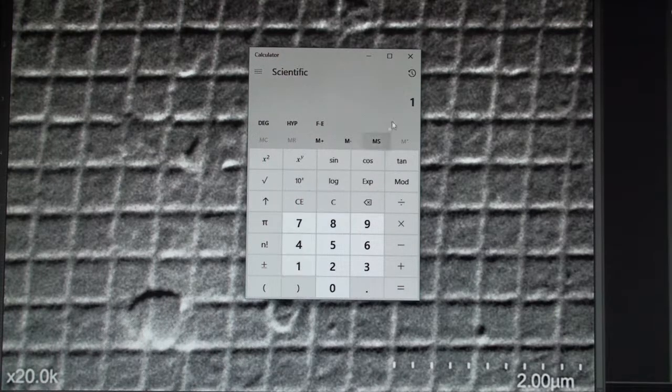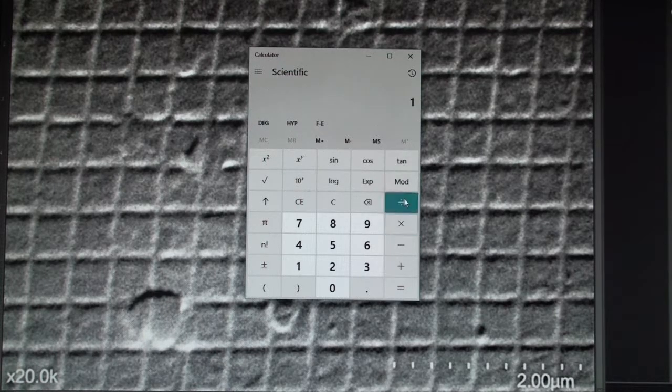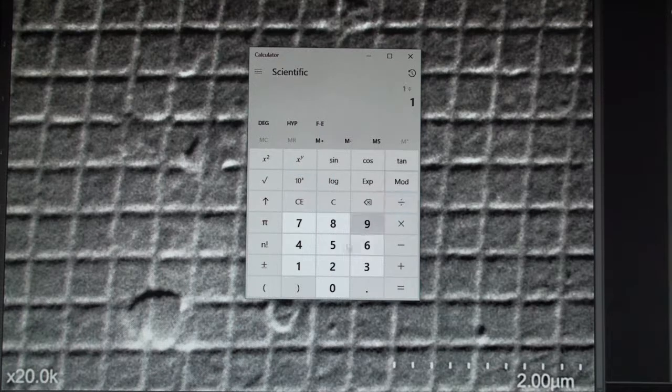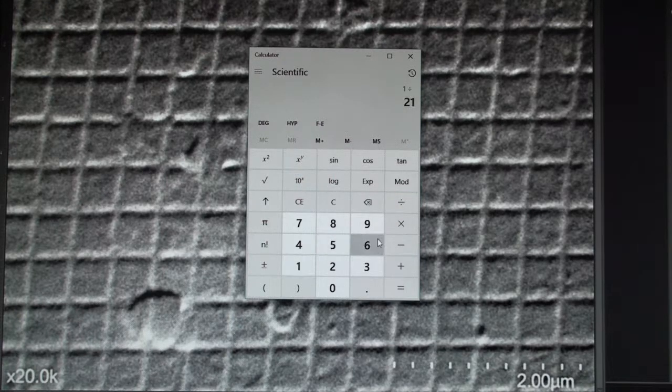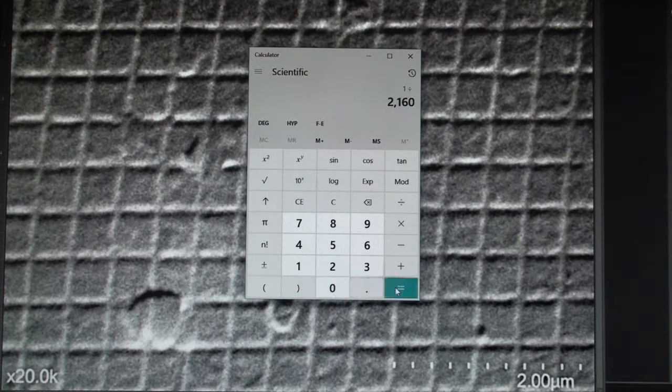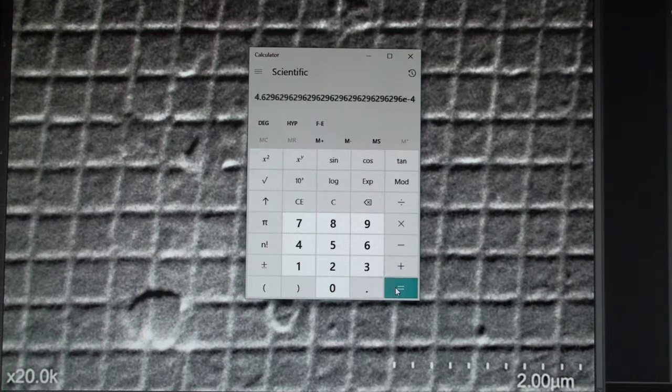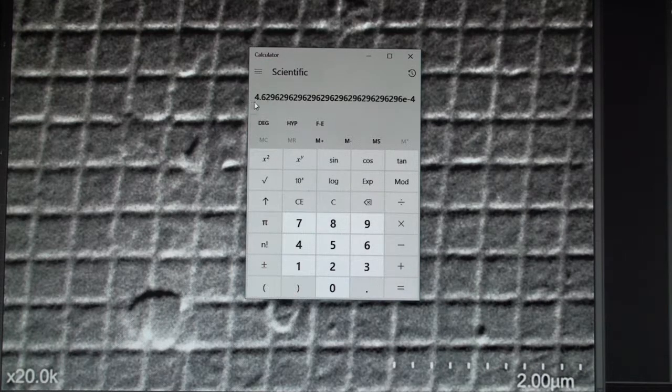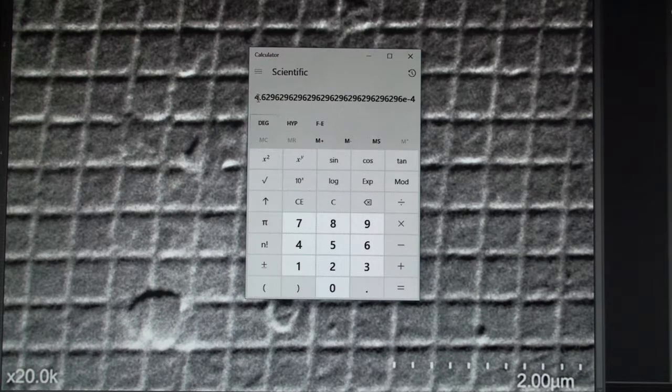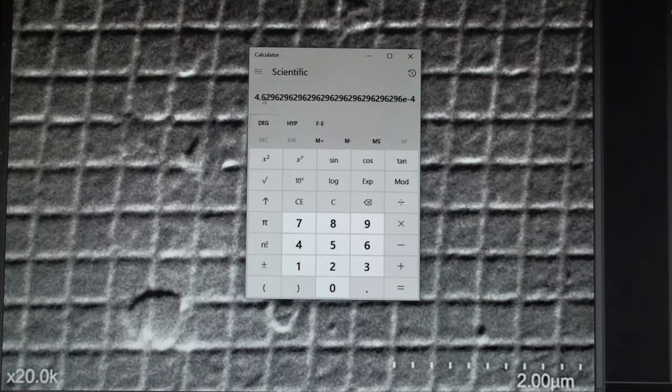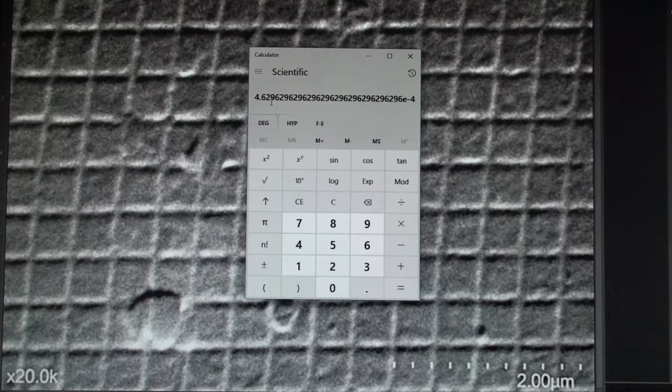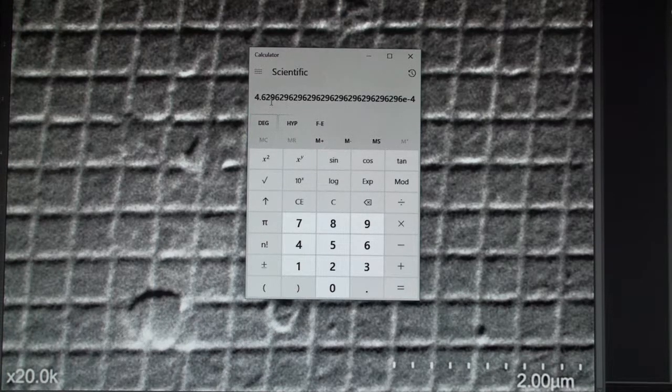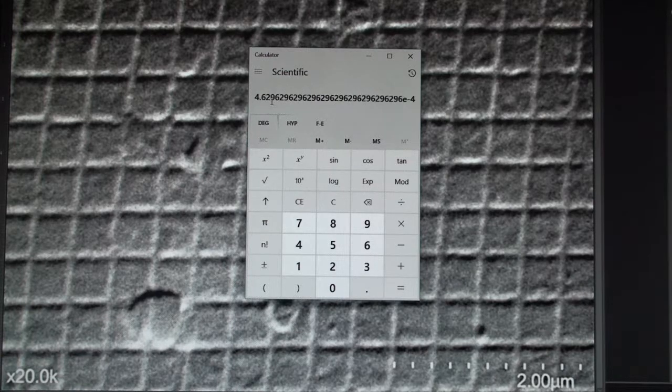Now, sometimes when you're calibrating your magnification on the microscope for digital image acquisition, it's going to want you to put in a distance of where you measure. And so each square, if I take 1 and divide it by 2160, I get 0.463 microns.